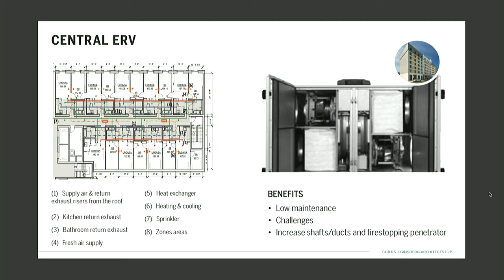So we're doing this. Now this we needed a determination on too. Because at the top, building department, except for a unitized in an apartment, does not allow you to combine kitchen and bathroom exhaust. But we want to minimize the number of holes through the roof, the number of ERVs. So what we did is we got permission above the top units, and we had to add height in the top floor. We connected the exhaust and ran through the ERV as one, and then the supply comes down as one. And DOB has let us do that now. We've gotten it at least twice, so I think they're fairly comfortable with it.